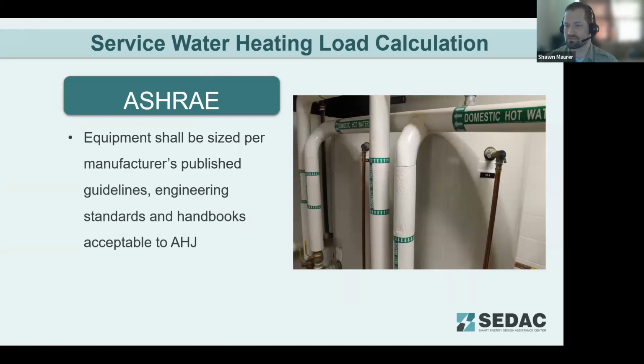For facilities such as what we've got pictured on the screen here, where you've got multiple storage tanks, if you need to reduce size, you could try isolating one or more of those tanks to see if all the tanks are still required based on the current operations and loads in the building for the given water consumption. Commonly with new fixtures, where less water is used at each fixture, your hot water capacity has been reduced over time. So particularly in existing buildings when looking at upgrades, ASHRAE does require that the domestic water system be properly sized. This is excluded from the IECC currently.